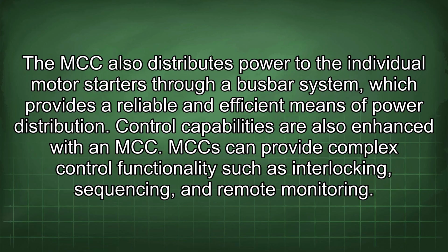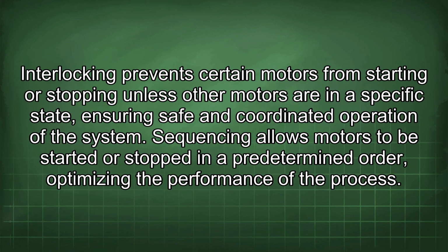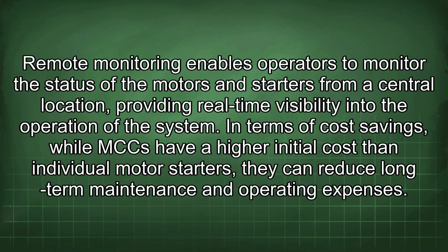An MCC can provide complex control functionalities such as interlocking, sequencing, and remote monitoring. Interlocking prevents certain motors from starting or stopping unless other motors are in a specific state, ensuring safe and coordinated operation of the system. Sequencing allows motors to be started or stopped in a predetermined order, optimizing the performance of the process. Remote monitoring enables operators to monitor the status of the motors and starters from a central location, providing real-time visibility into the operation of the system.